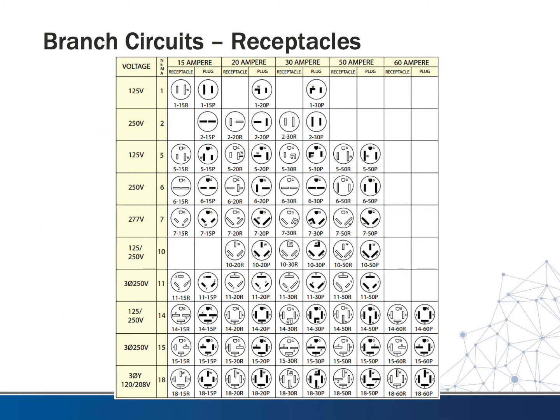This table shows the standard NEMA outlet and plug configurations. Down the left side is the voltage needed — single phase and three phase. Across the top is the maximum amperage that the plug would be rated for. There's a NEMA number associated with each row, and in each column there are double columns under each heading: on the left is the receptacle — what would be in or on the wall — and the plug is what actually goes on the end of the cord.